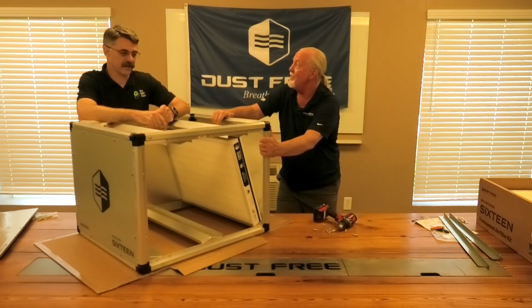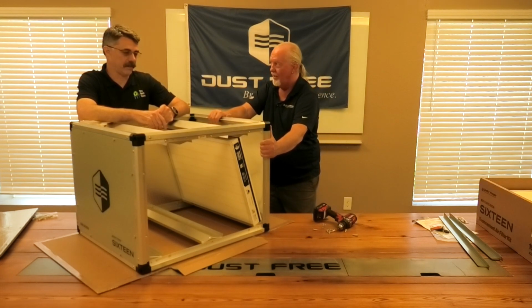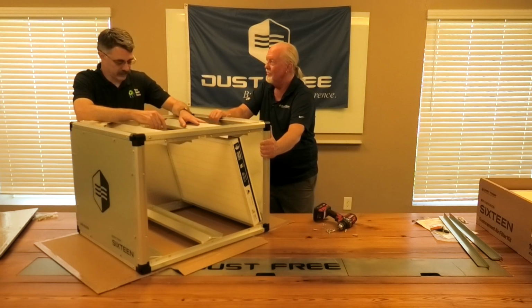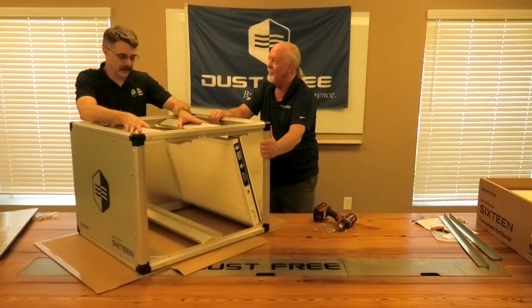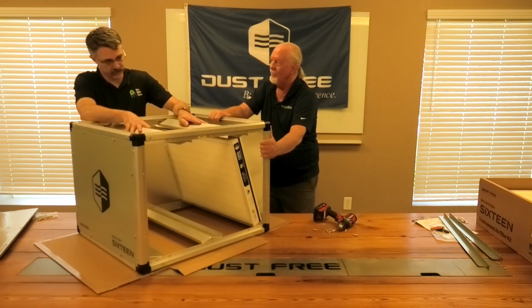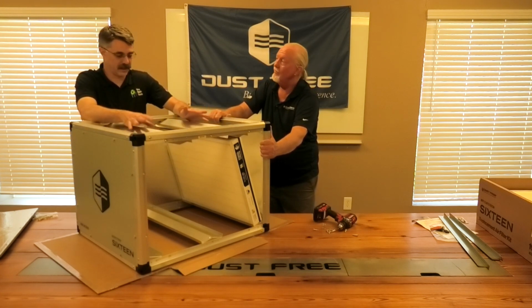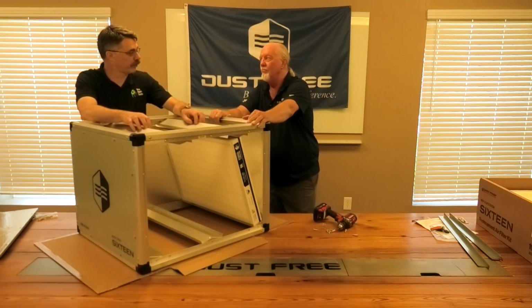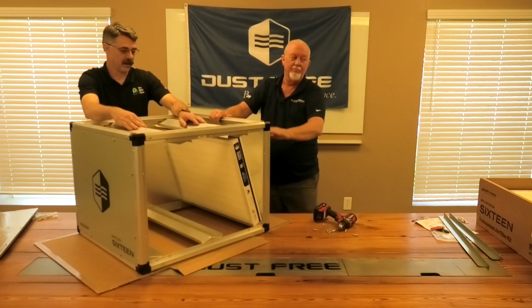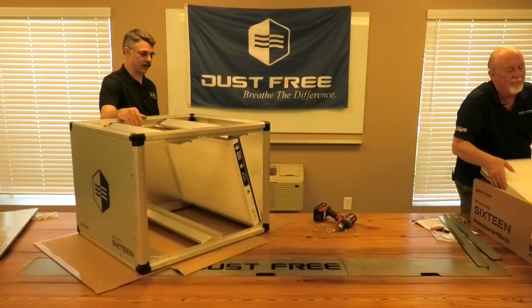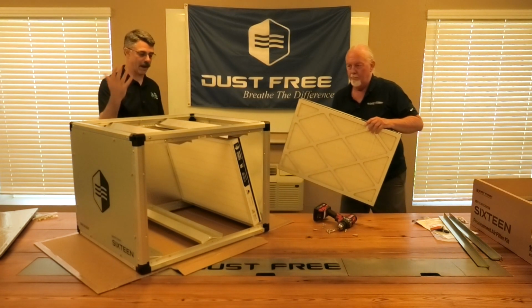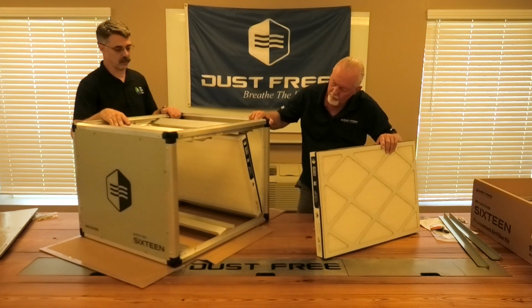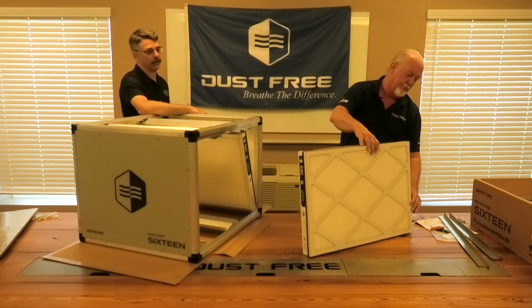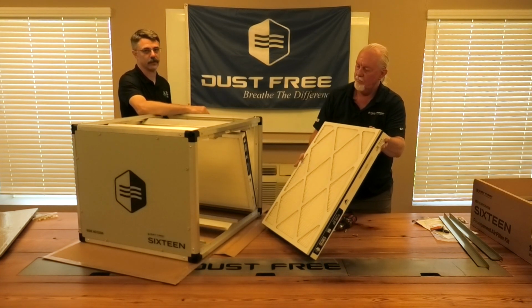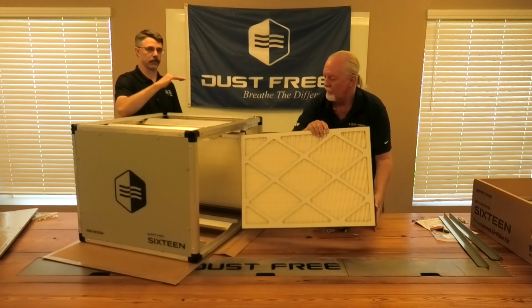That's a nice snug fit. That makes a lot of sense, and I love that fit in there. Those are the filter racks, the rails that hold the filters in. I'm gonna go with probably Devin's gonna check me on this, 18 gauge aluminum. They're sturdy, they don't flex, there's no yaw in that at all. It's solid, so when those filters slide in there, they're fitting tight. One of the things, test-wise, there's no bypass on this around the filters, because of the way it was built. So they get that high MERV rating actually when installed in the system, rather than just the MERV rating on the filter.